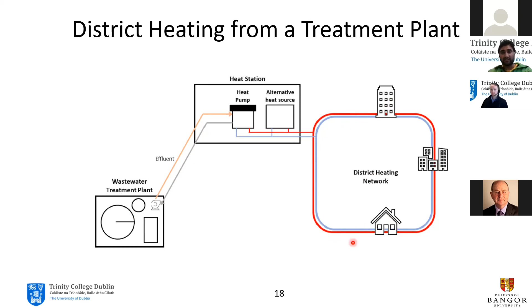So we are taking advantage of the high volume flow rate of the hot wastewater, and via a pump we circulate the effluent, and it goes directly to the heat pump unit. The recapture of heat from the wastewater takes place in this heat pump, which then gives a direct energy input to the auxiliary heating unit to reduce its heating load requirements. And this bulk heat goes directly for district heating for various industrial and commercial hubs, as well as the residential sectors. So this is a major advantage: we can recover the heat and use it for district heating when a high volume of wastewater is available.